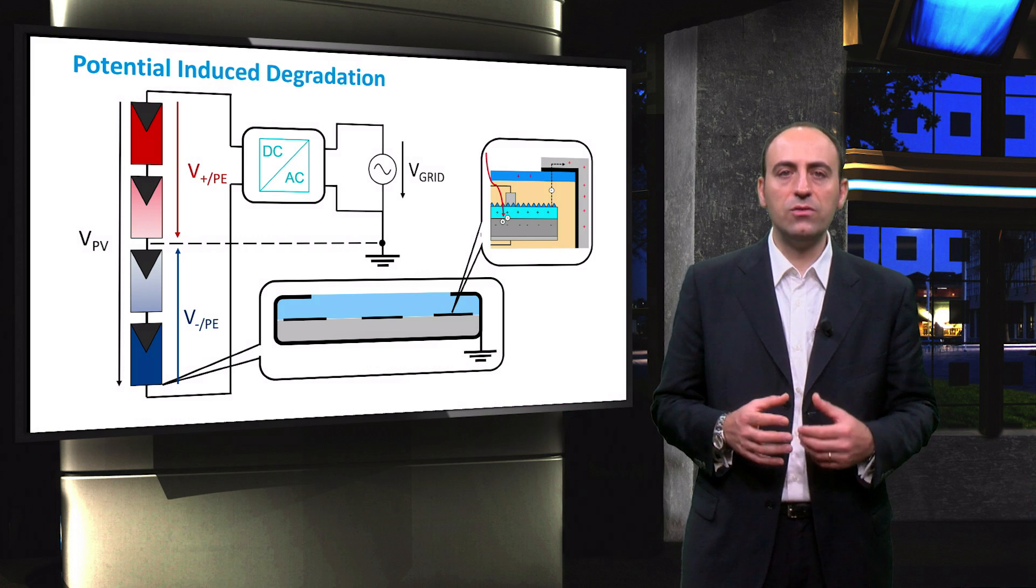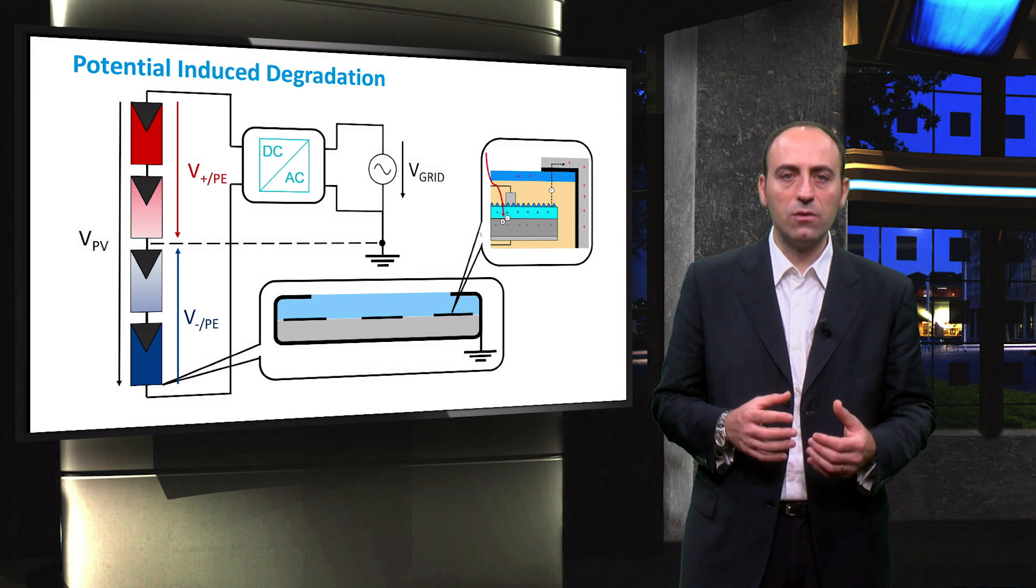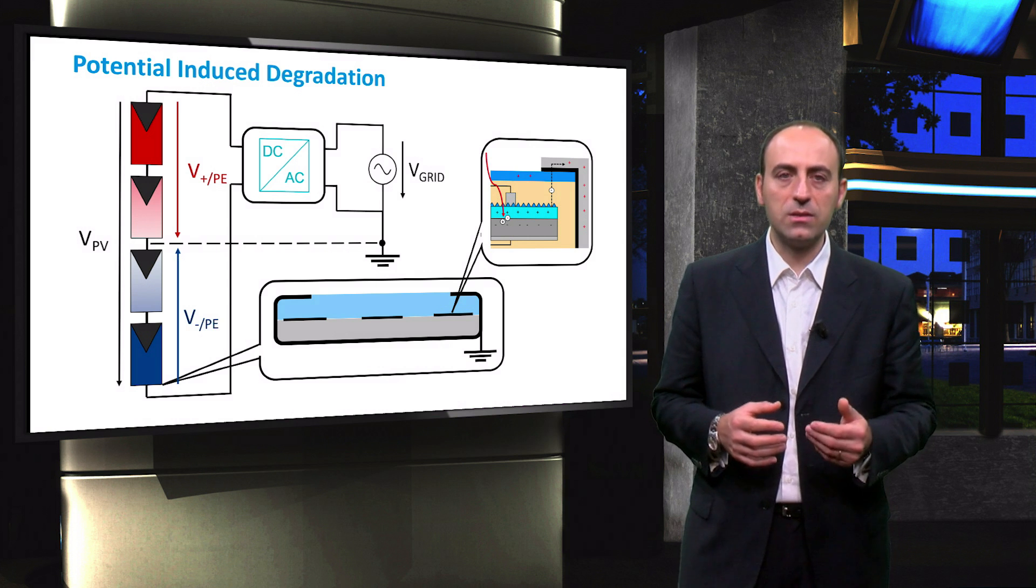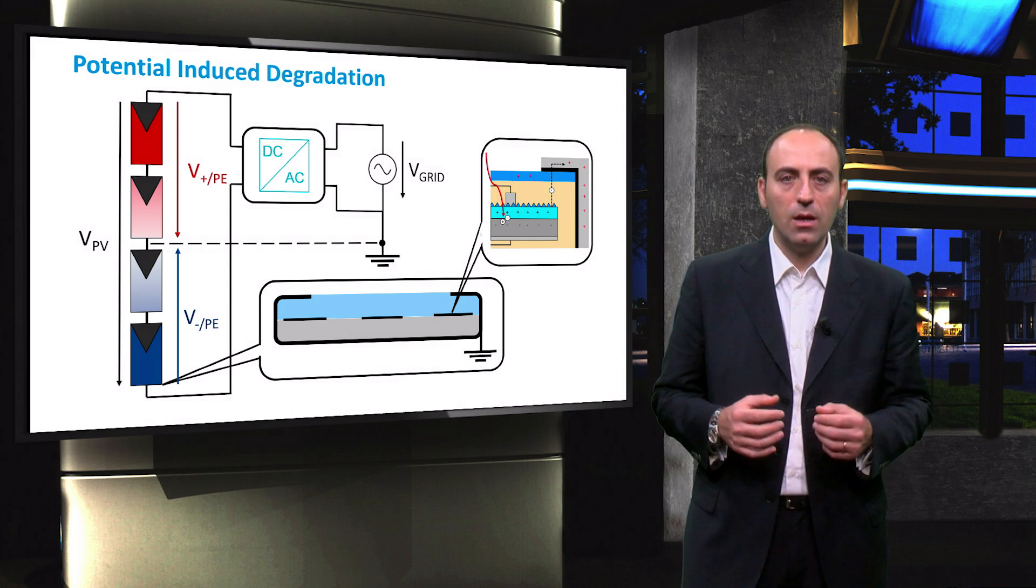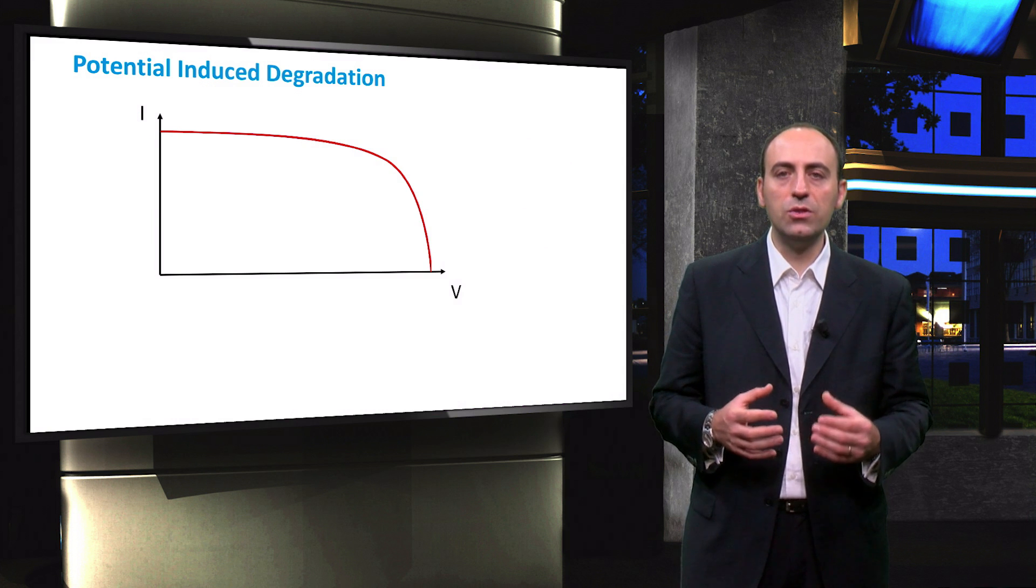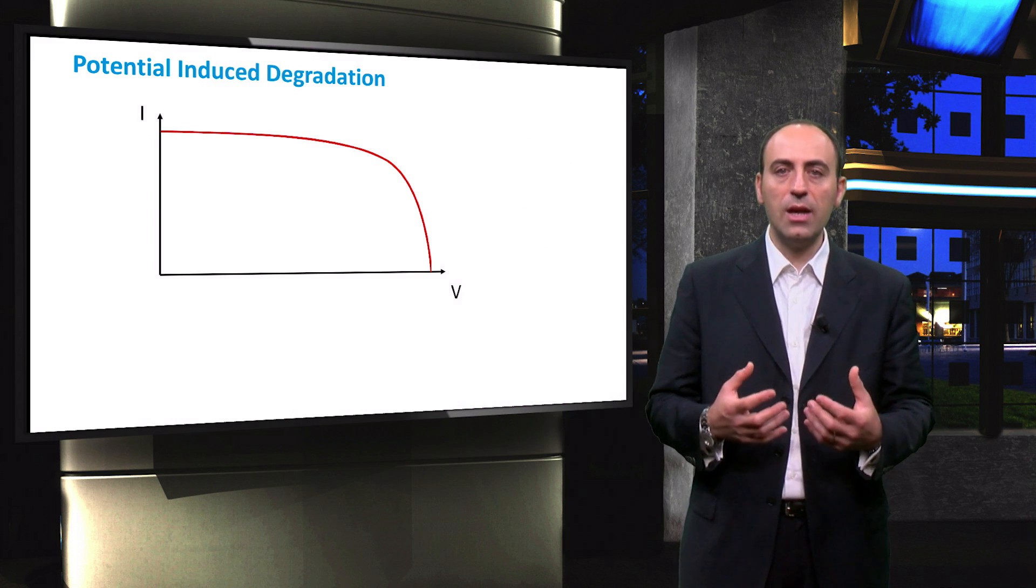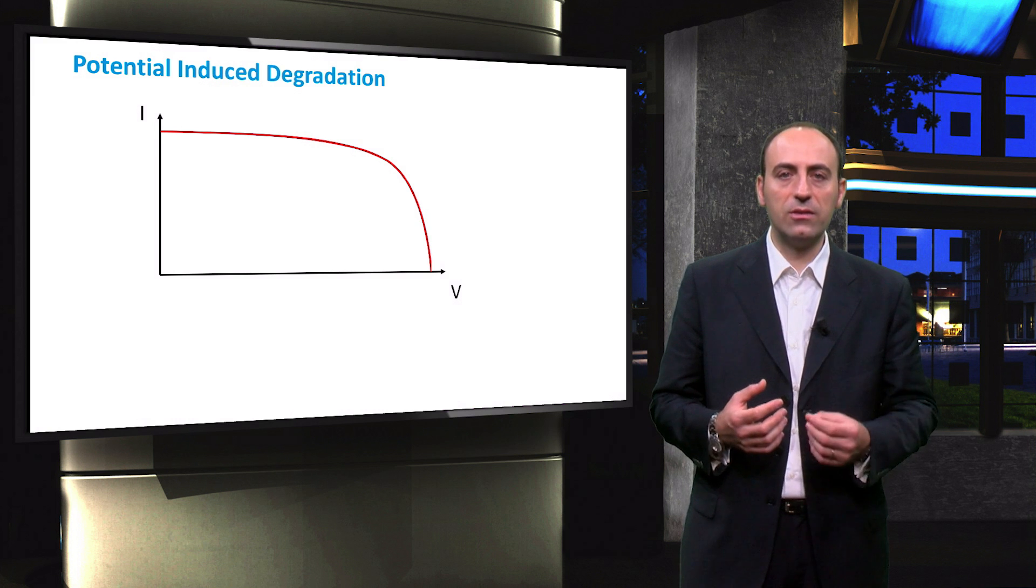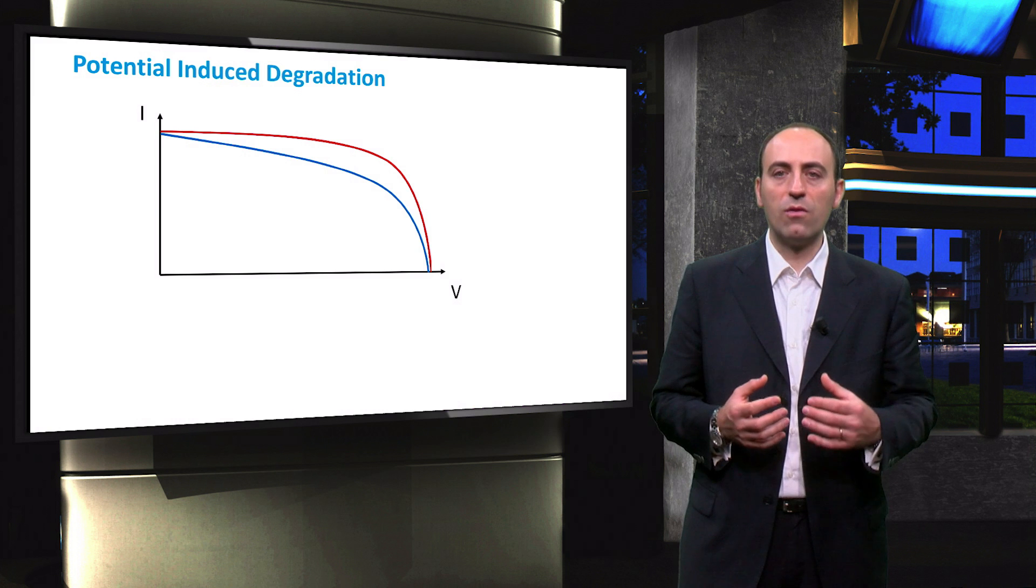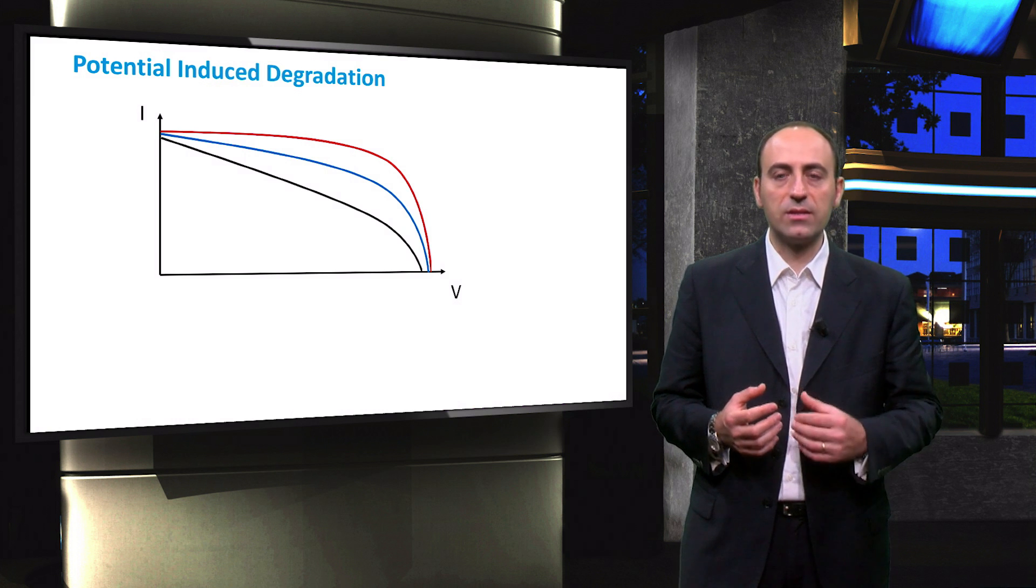The ions are driven from the semiconductor material towards other elements of the module, like glass, mount, and frame. This effect causes the module power output capacity to reduce because the polarization can adversely alter the characteristic curve of the PV cells. The curve tends to become more flat as the degradation effects increase.